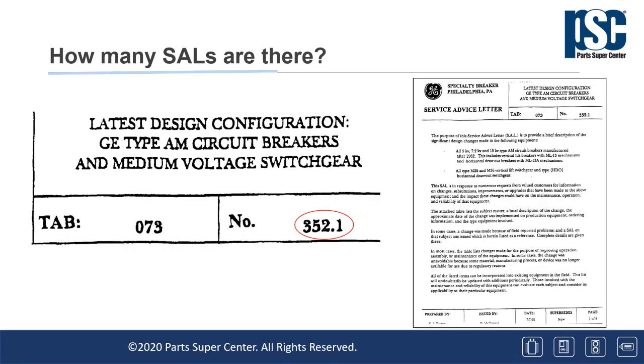While there are hundreds of service advisory letters, SALs for short, not all apply to every model and rating of Magneblast switchgear and circuit breakers. There's one granddaddy of all the service advisory letters. It's SAL 352.1. It's a summary of the most important service advisory letters related to Magneblast breakers and switchgear. It's presented in a table format that includes effective dates as well as model information that is applicable to the specific switchgear and breaker. It also includes ordering information when parts will be necessary.